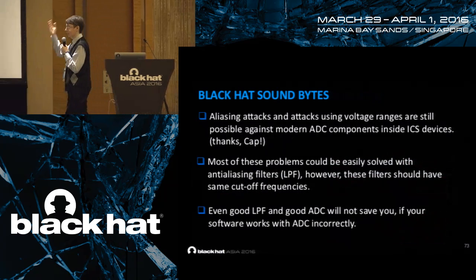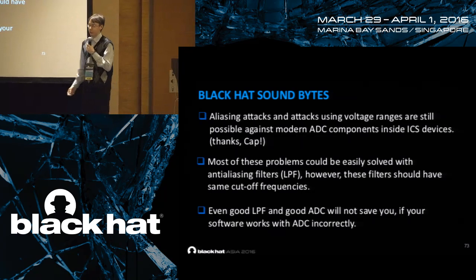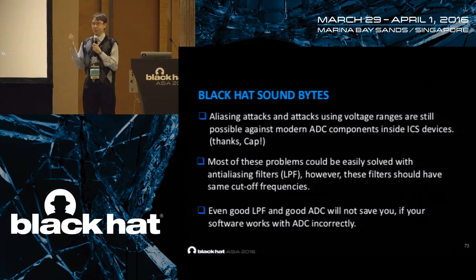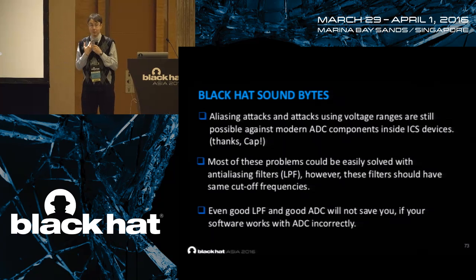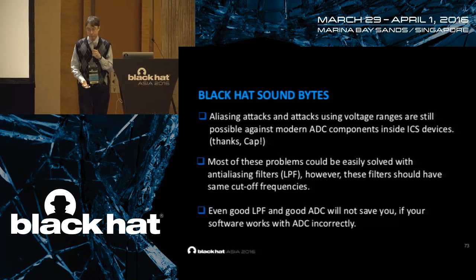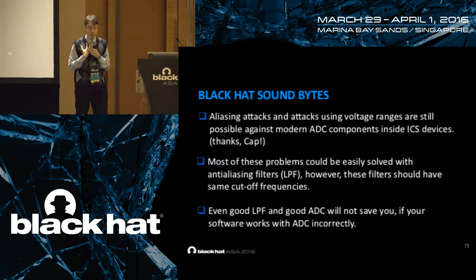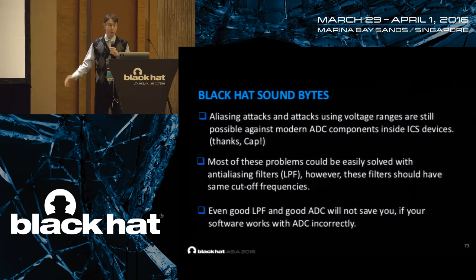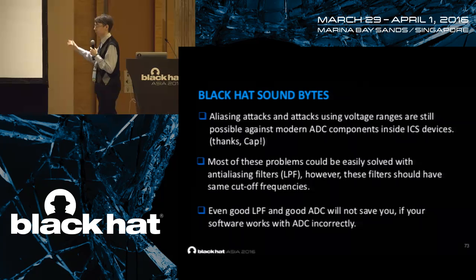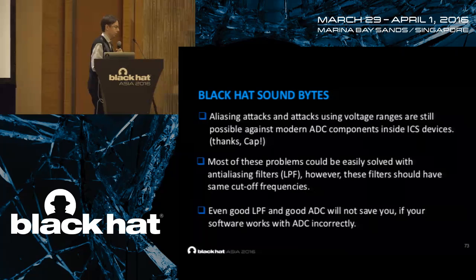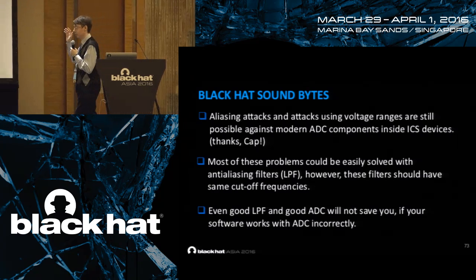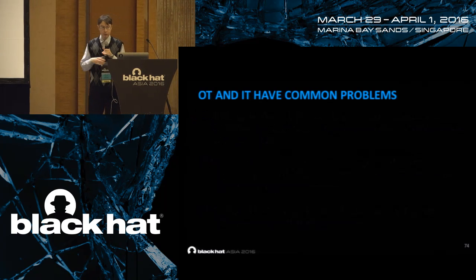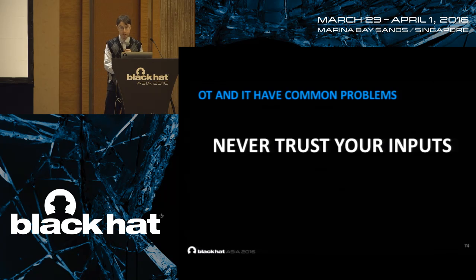Black hat sound bites — the captain slide: aliasing attacks and attacks using voltage ranges are still possible. Maybe it's obvious, but as you can see, they are still possible against modern ADC components inside ICS devices. Most of these problems could be easily solved with anti-aliasing filters. However, these filters should have the same cutoff frequencies or they are useless. And even a good LPF and ADC will not save you if your software works with ADC incorrectly — if it sleeps, calls it at incorrect times, does not average, does not use certain randomness, or uses incorrect normalizing. This is where OT and IT have common problems: never trust your inputs.